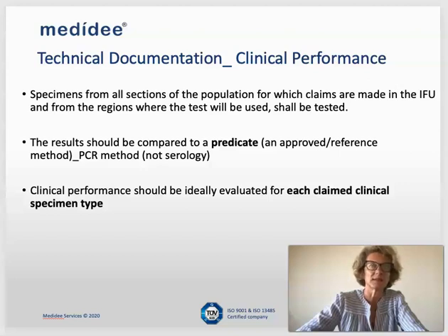Normally, when conducting clinical performance studies, we should use specimens from all sections of the population for which the claim is made in the instructions for use of the device. For instance, if the test is intended for a European population, I will expect to see studies performed in a European population and not on an Asian population, to give you an example.